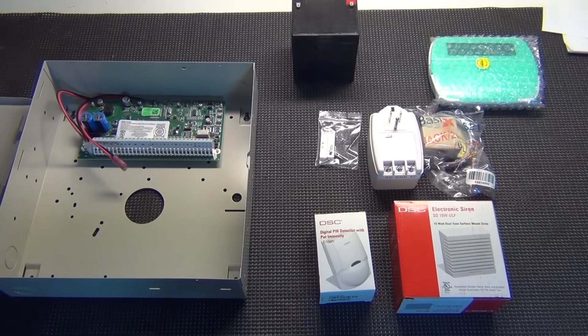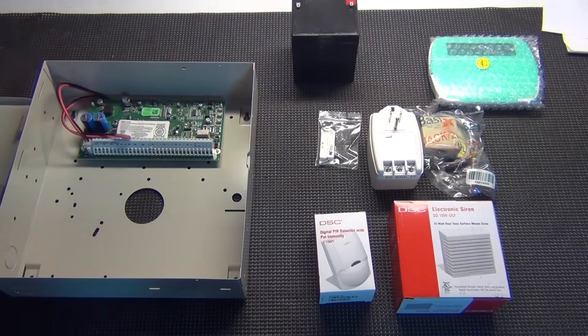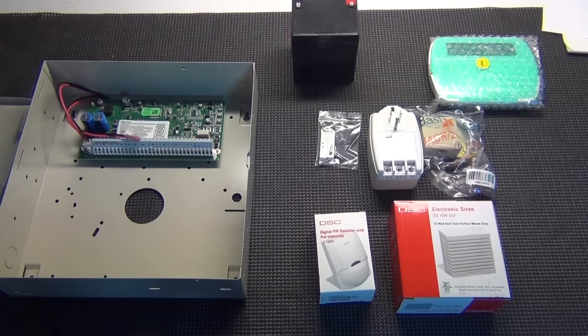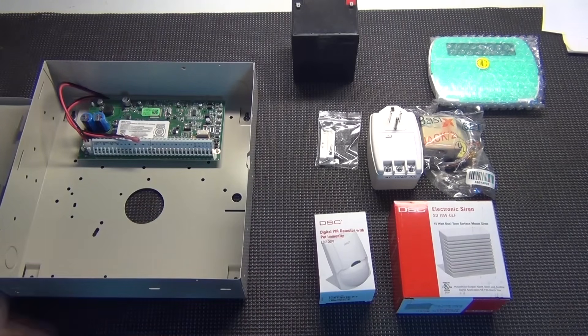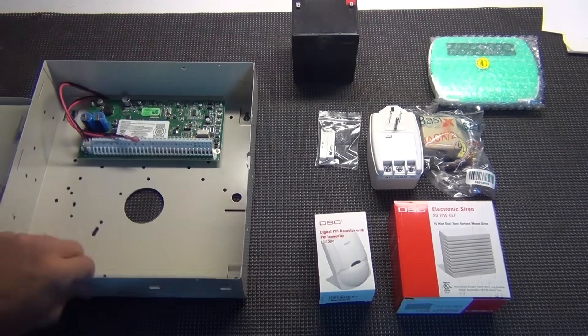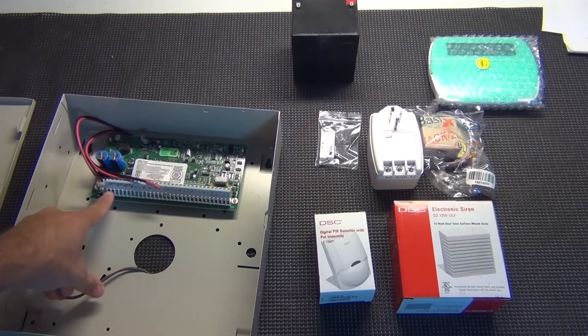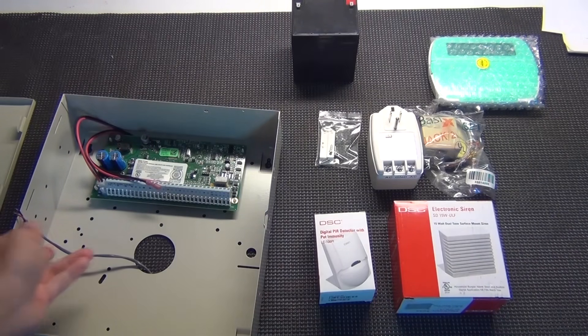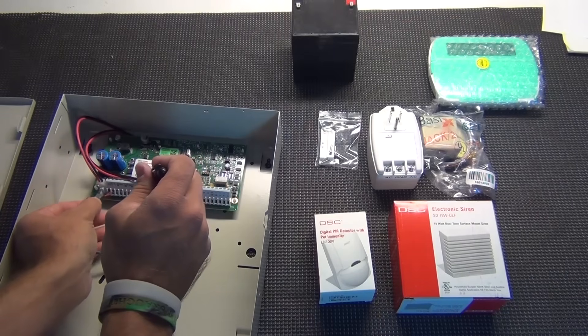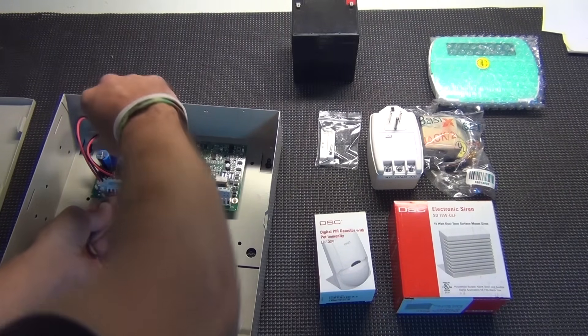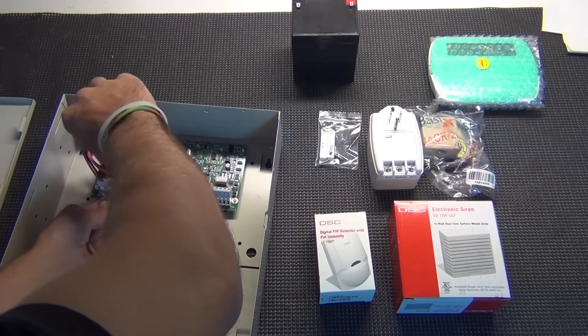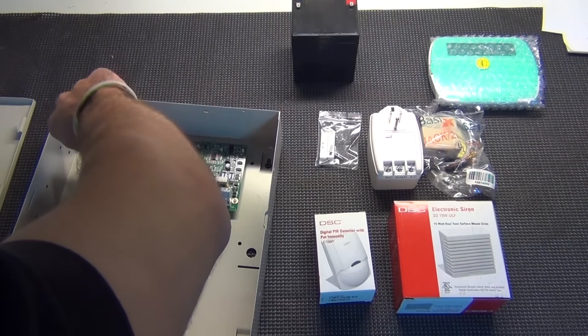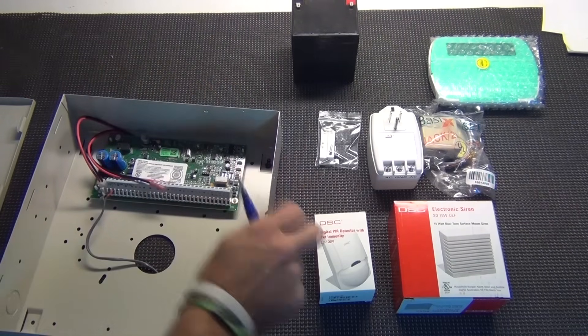Next is you need to connect your AC wire. Make sure nothing is plugged in. Do not plug your transformer in or anything like that. You need two wires right there, and this is already ran inside your panel. All right, you put the two wires into the terminals that is marked AC AC. And we'll do that. And then we'll tighten down the screws. It's non-polarity, so don't worry.